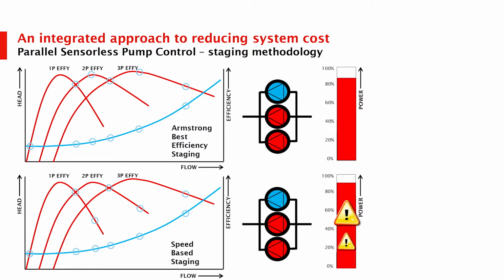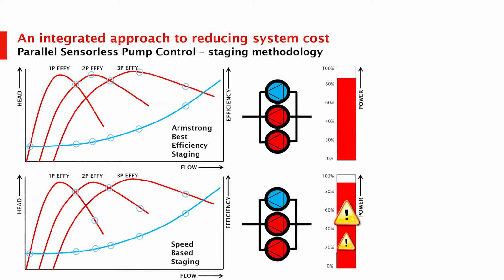The way BAS systems traditionally work, and still work in the vast majority of buildings, is that they ramp up the equipment to somewhere between 90 and 95%, maybe 100% capacity, before they dispatch or sequence a second piece of equipment. Speed-based control is the way things have been working, and technically it works fine. On the top is what we would do with parallel pumping, or parallel dispatch of any equipment. In the first situation, both pieces of equipment will run up to about 3/4 of their speed, and you get the same flow in either situation. The flow is the blue curve on both graphs.